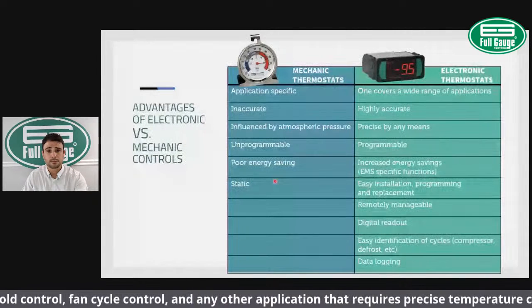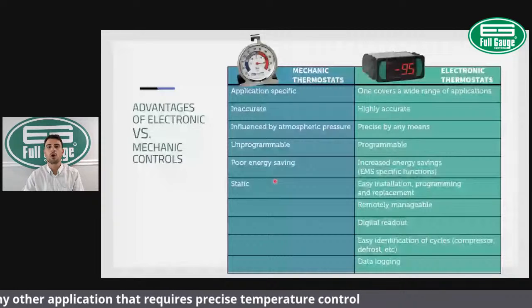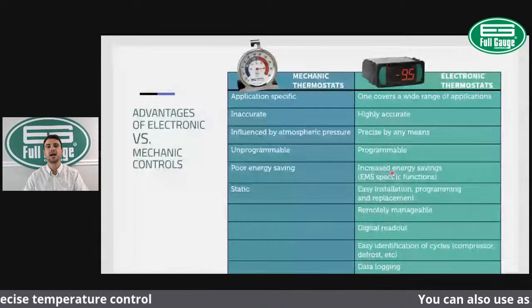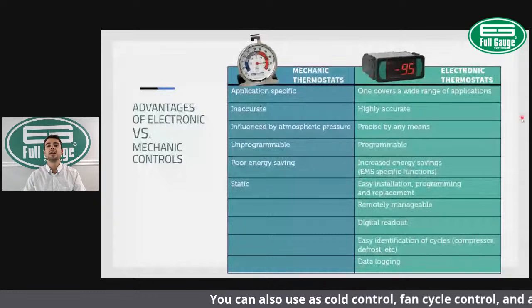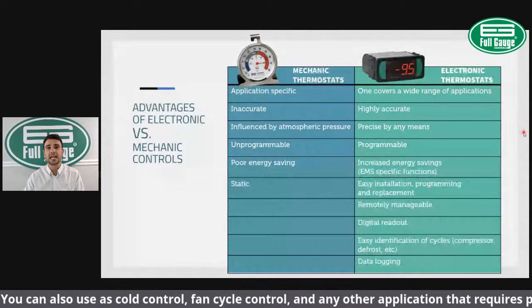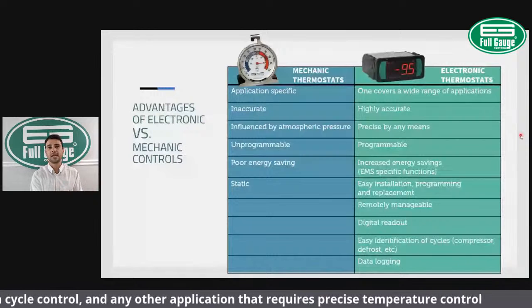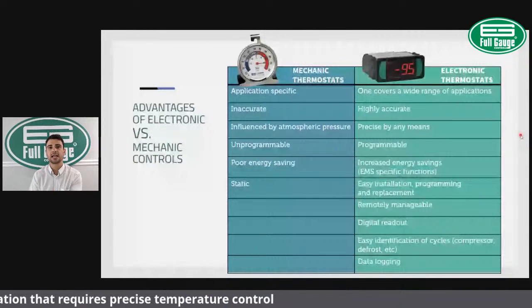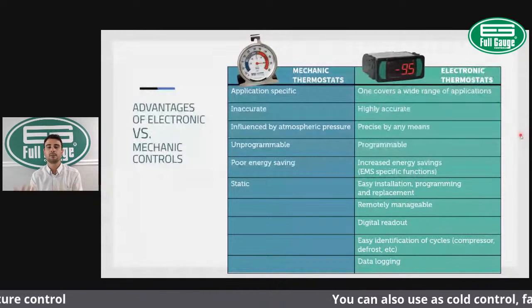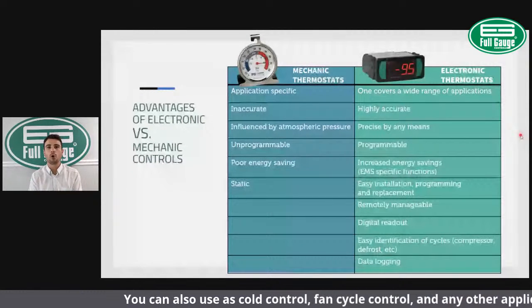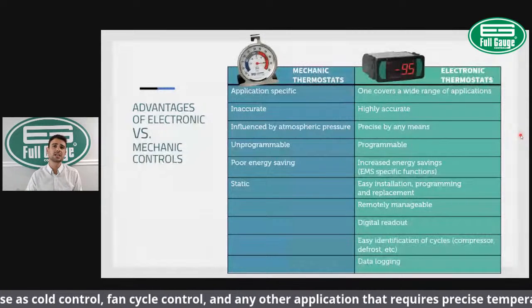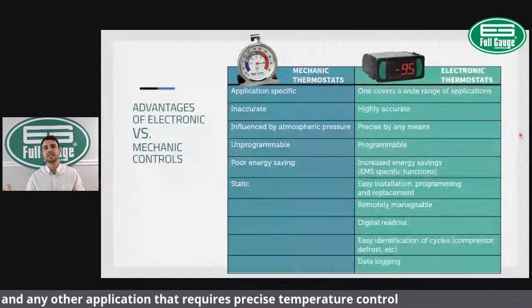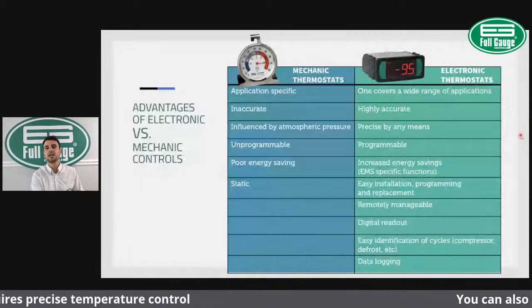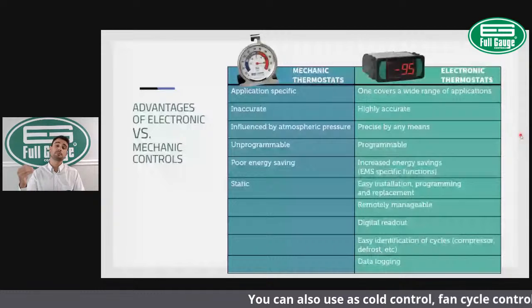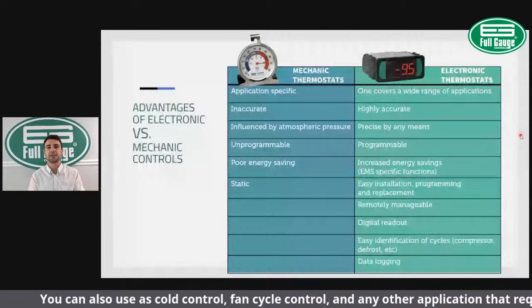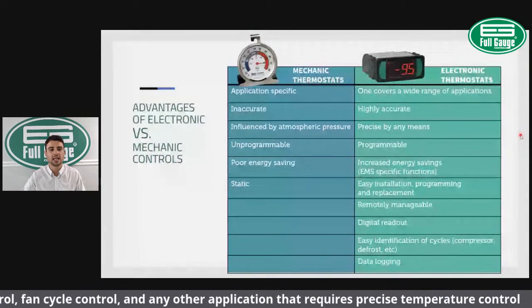Another thing is the precision. Digital controls are more accurate than the mechanical controls, which provides a more stable temperature control. In addition to that, you get huge energy saving only by switching from the mechanical over to microprocessor-based technology to control temperature. So that precision actually provides more energy saving. Those are the three main reasons why we've seen this transition over the last few years: versatility, energy saving, and accuracy. Those would be the points that I would highlight for that transition.